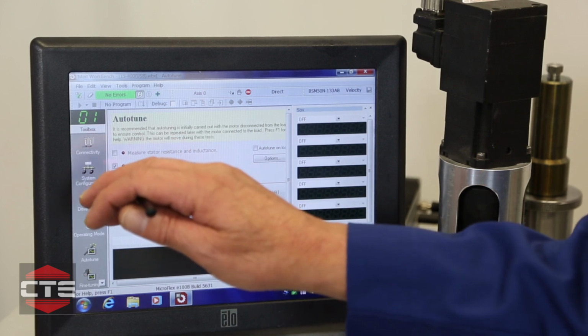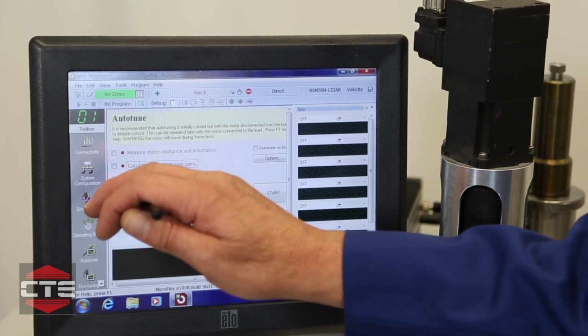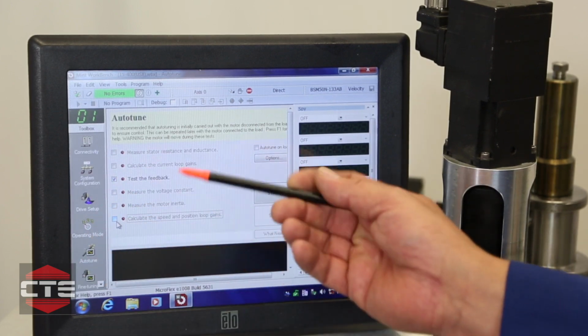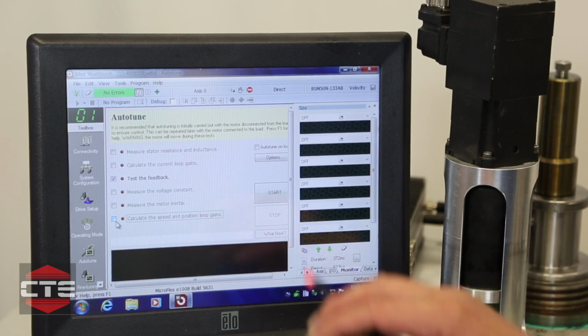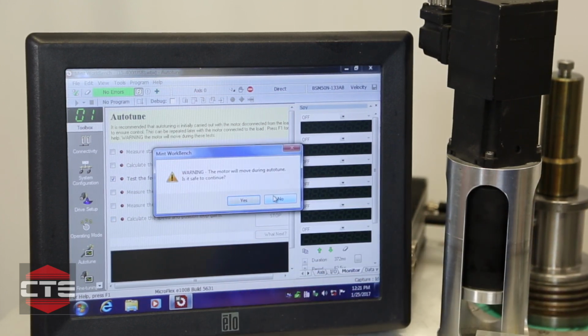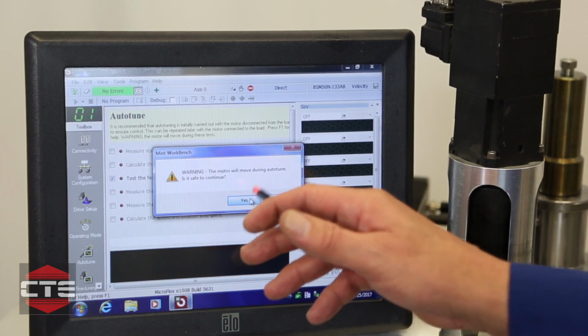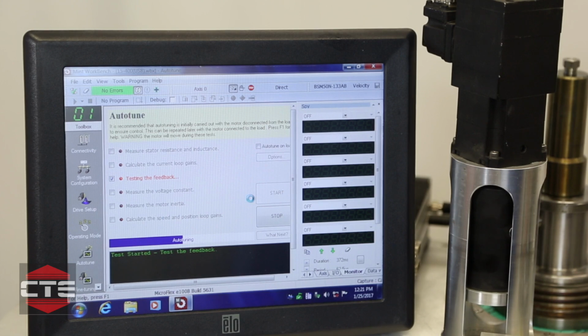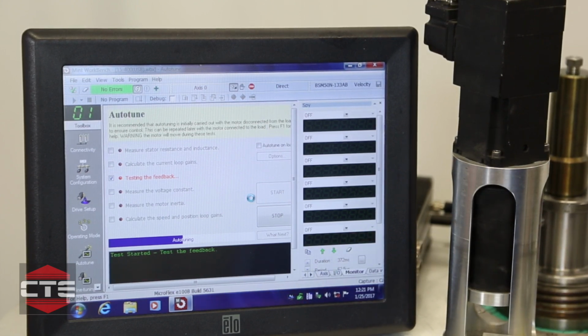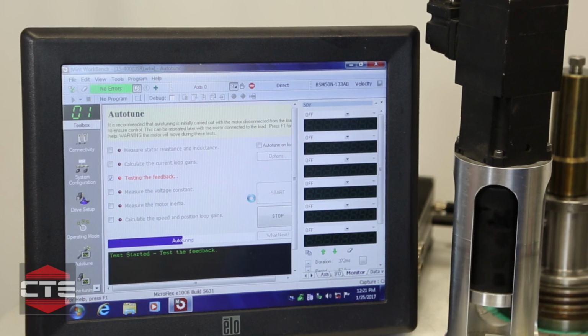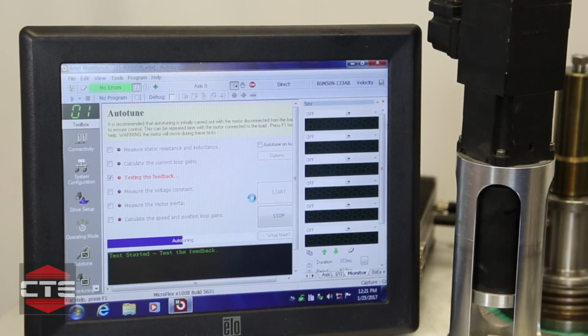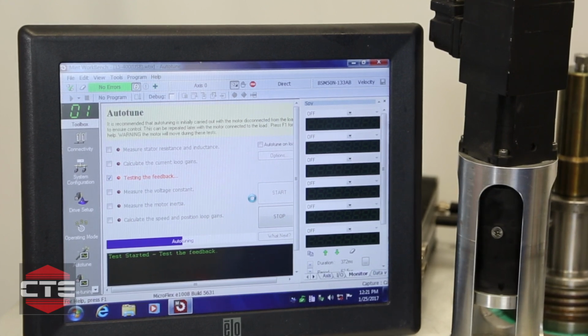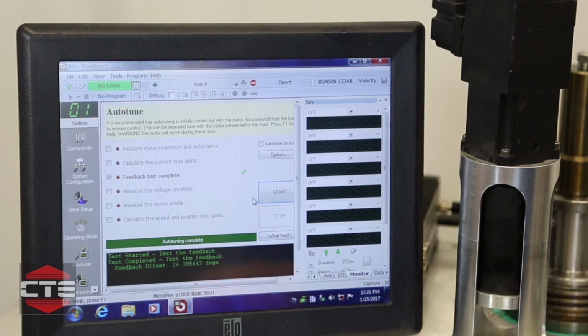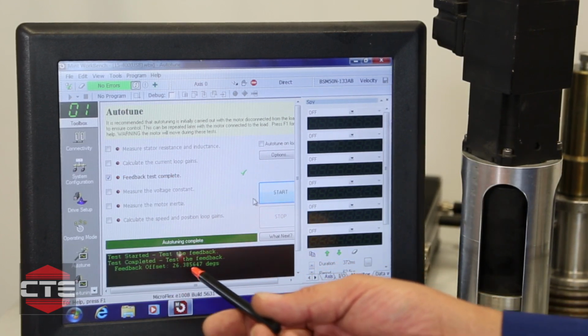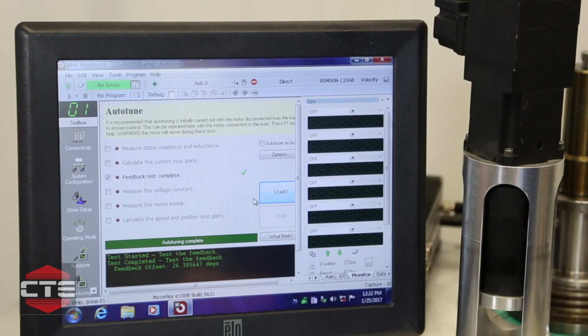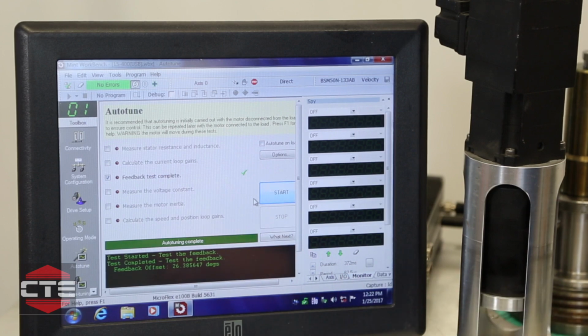For your auto-tune, you want to make sure the only box you have checked on here is test the feedback. So uncheck everything else, as you can see. Only the test the feedback box is checked. Start, it will prompt you to tell you that the motor is going to turn. This thing's not going to spin at any high speeds. Select yes, and if you watch the motor, you're going to get rotation in one direction, followed by rotation in the opposite direction. And then you'll get some information down here which you don't need to know. The only thing you need to watch for is this right here, no errors. As long as that box is green, then the motor has been auto-tuned.